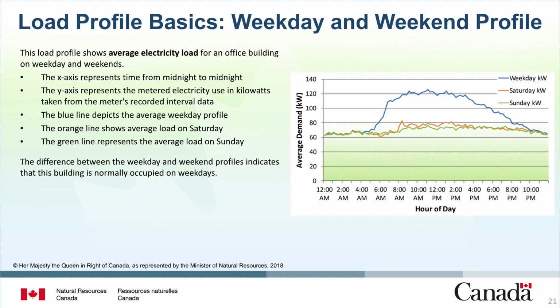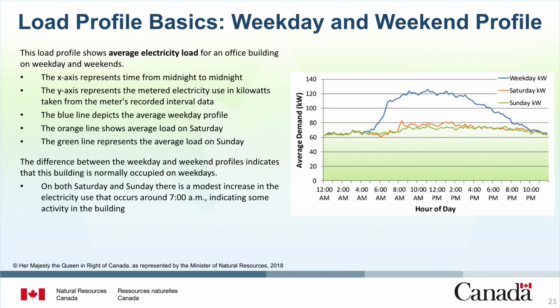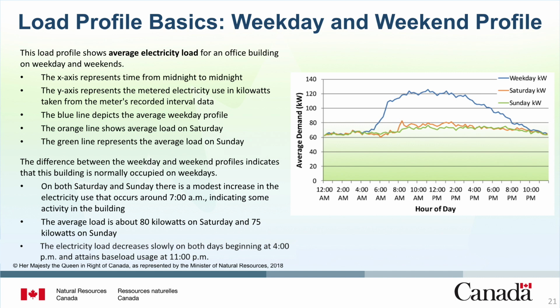The difference between the weekday and weekend profiles indicates that this building is normally occupied on weekdays. On both Saturday and Sunday, there is a modest increase in the electricity use that occurs around 7 a.m., indicating some activity in the building. The average load is about 80 kilowatts on Saturday and 75 kilowatts on Sunday. The electricity load decreases slowly on both days beginning at 4 p.m. and attains base load usage at 11 p.m.